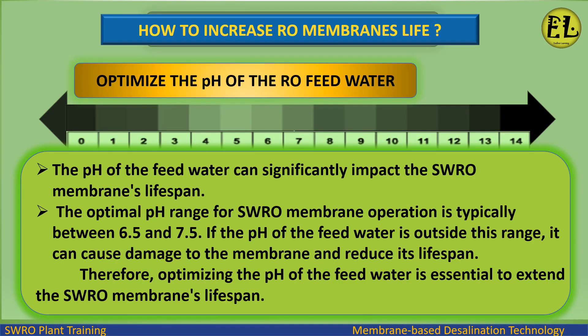The pH of the feed water can significantly impact the SWRO membrane's lifespan. The optimal pH range for SWRO membrane operation is typically between 6.5 and 7.5. If the pH of the feed water is outside this range, it can cause damage to the membrane and reduce its lifespan. Therefore, optimizing the feed water pH is essential to extend the SWRO membrane's lifespan.